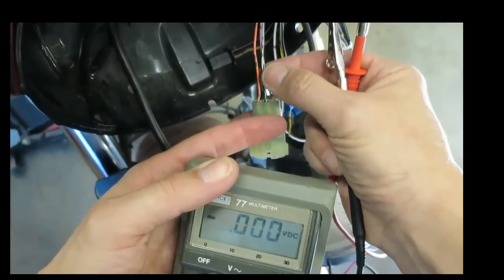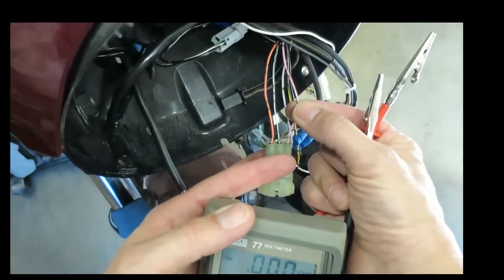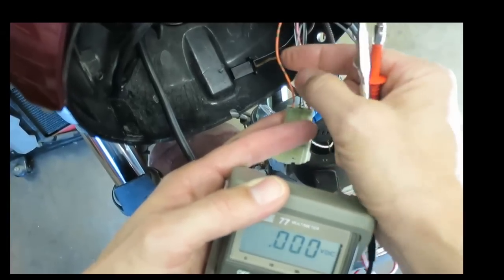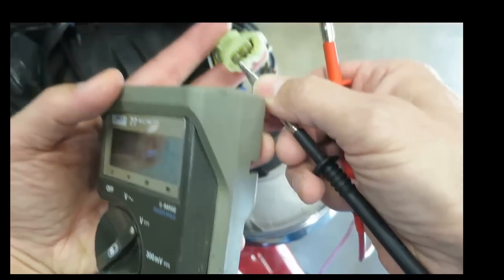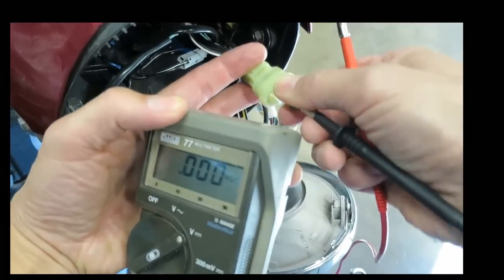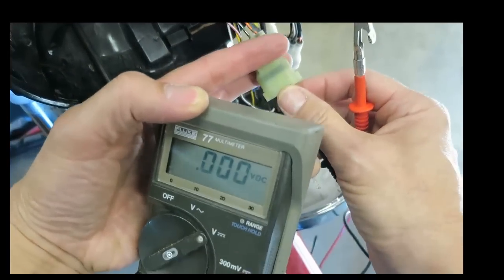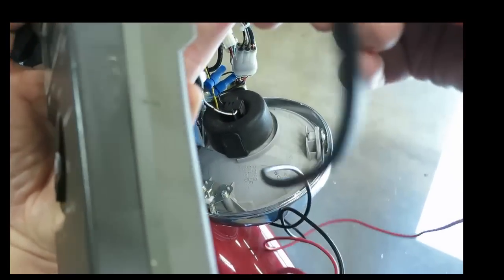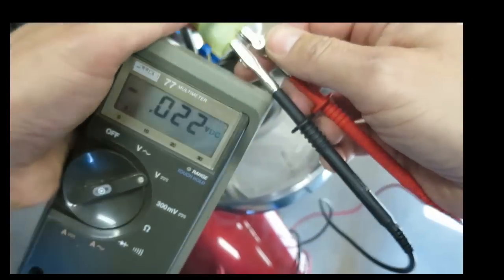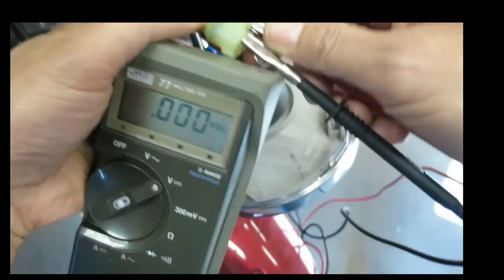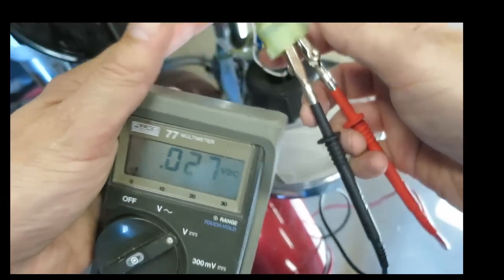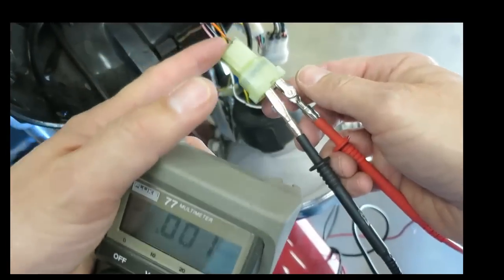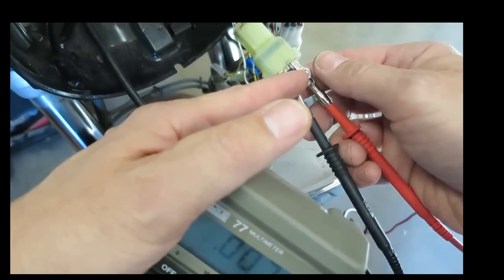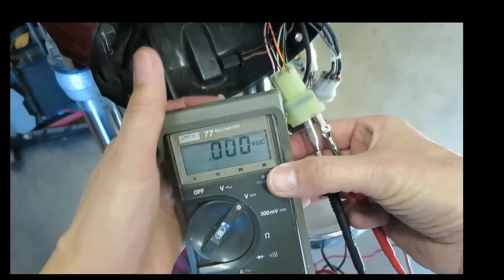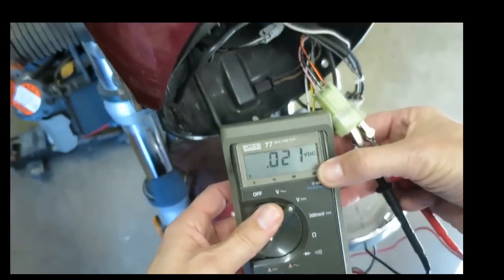Pink is the sensor signal out, black white is ground, and orange red is power. So we'll connect the black on the meter to black, white on the plug, red on the meter to orange red. Now these probes are very close to each other. There is a current limit resistor, a 100 ohm resistor inside the gauge on this line. So even if you short these, no damage will be done. But in general, you'd like to avoid doing that.